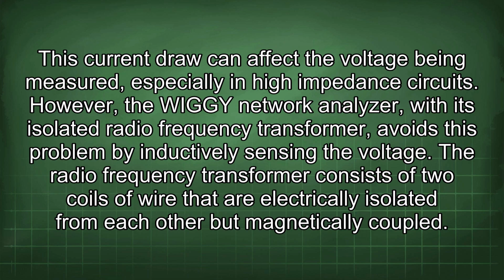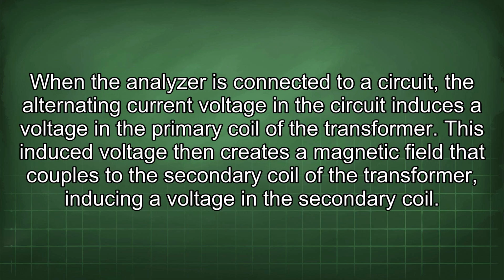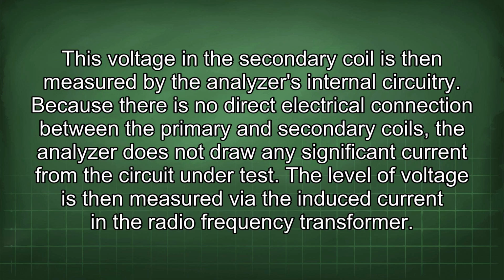The radio frequency transformer consists of two coils of wire that are electrically isolated from each other but magnetically coupled. When the analyzer is connected to a circuit, the alternating current voltage in the circuit induces a voltage in a primary coil of the transformer. This induced voltage then creates a magnetic field that couples to the secondary coil of the transformer, inducing a voltage in the secondary coil. This voltage in the secondary coil is then measured by the analyzer's internal circuitry. Because there is no direct electrical connection between the primary and secondary coils, the analyzer does not draw any significant current from the circuit under test.